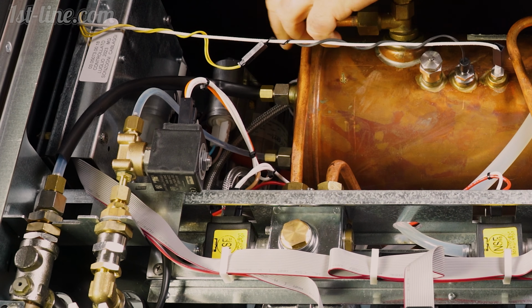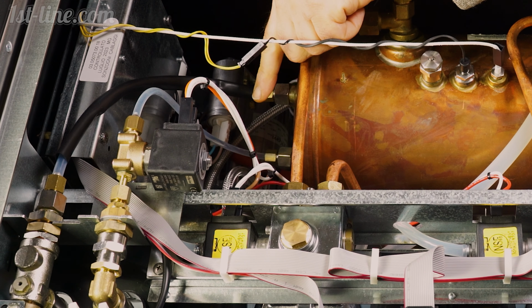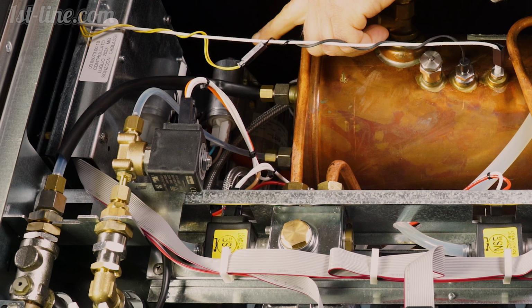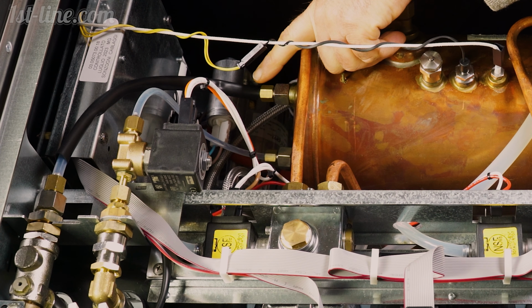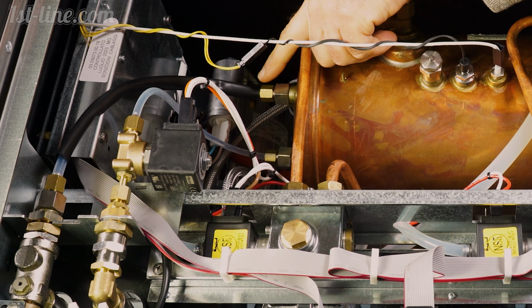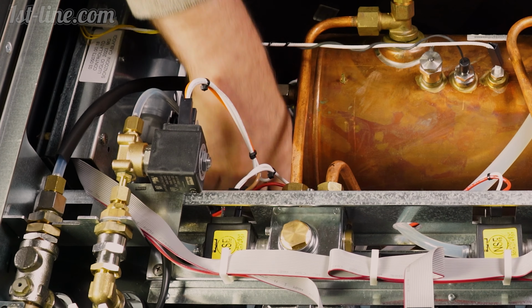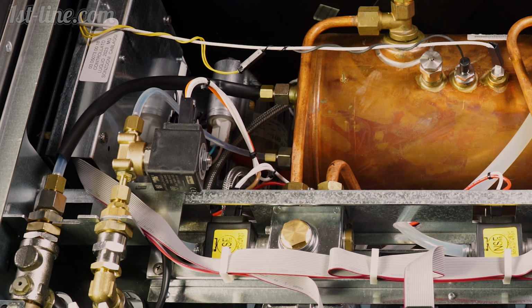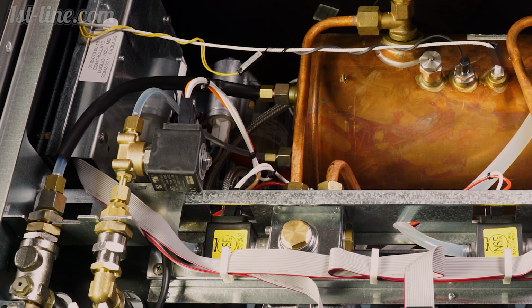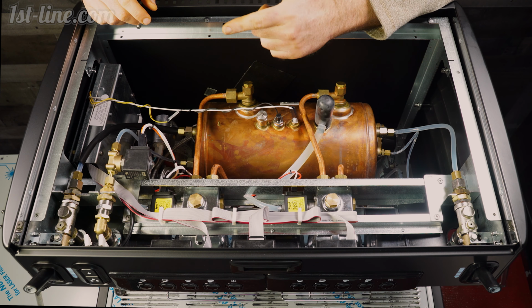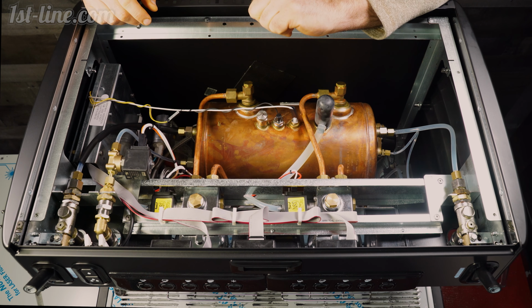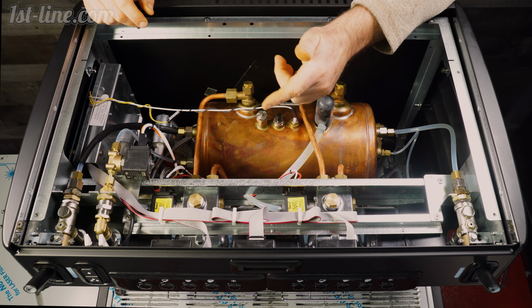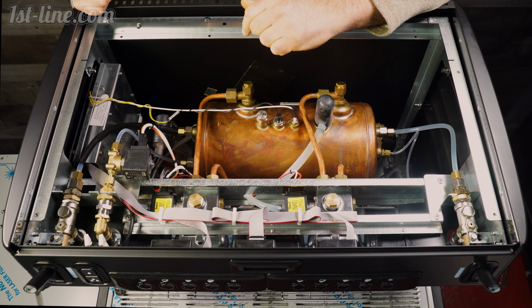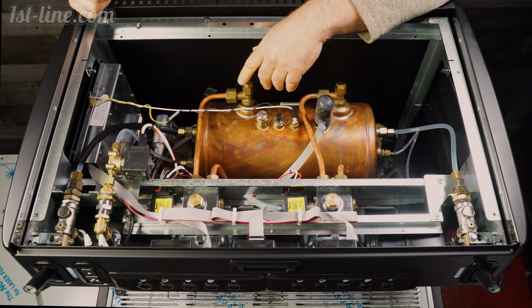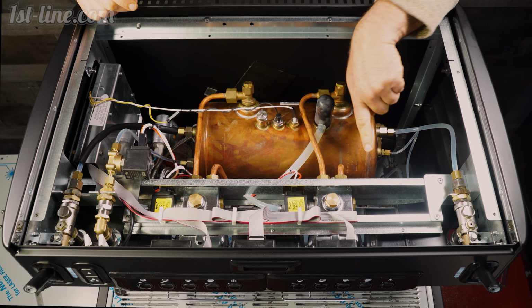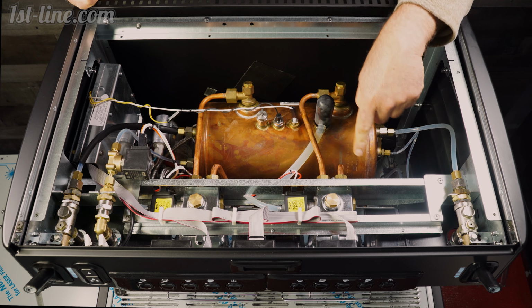On this side you have your rotary vane pump. There are different size rotary vane pumps - this looks like the 100 to 200 liter size, probably the 200. The adjustment is way down in here. There's a little holding nut you loosen, then turn it counterclockwise to bring the pressure down, or clockwise on the screw to increase the pressure. Typically you want to get it around 9 bar, using the pump pressure gauge on this side.